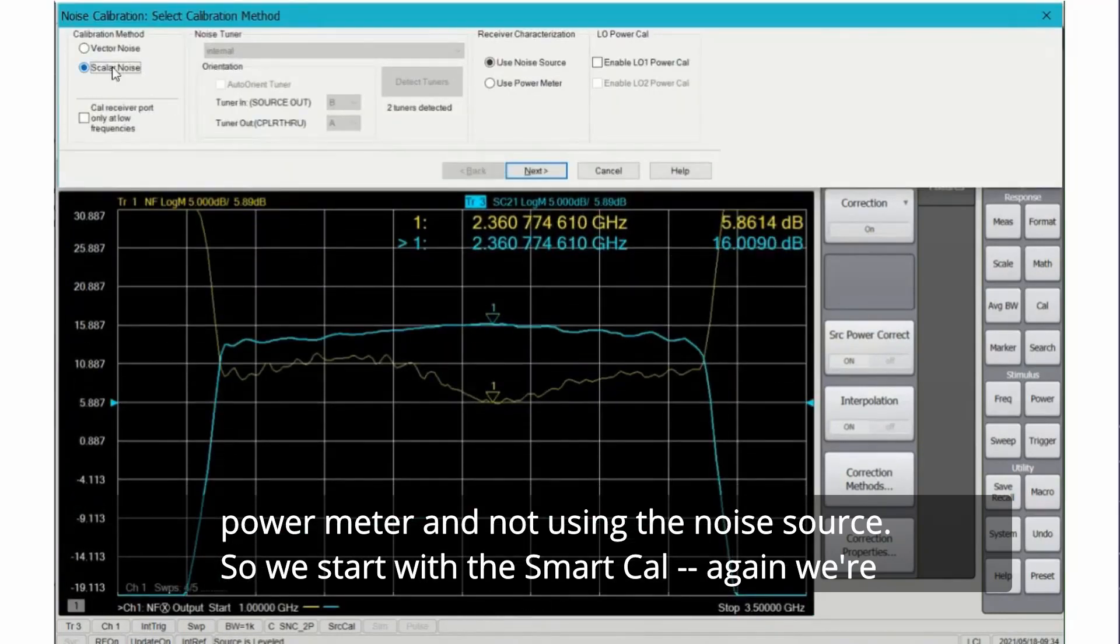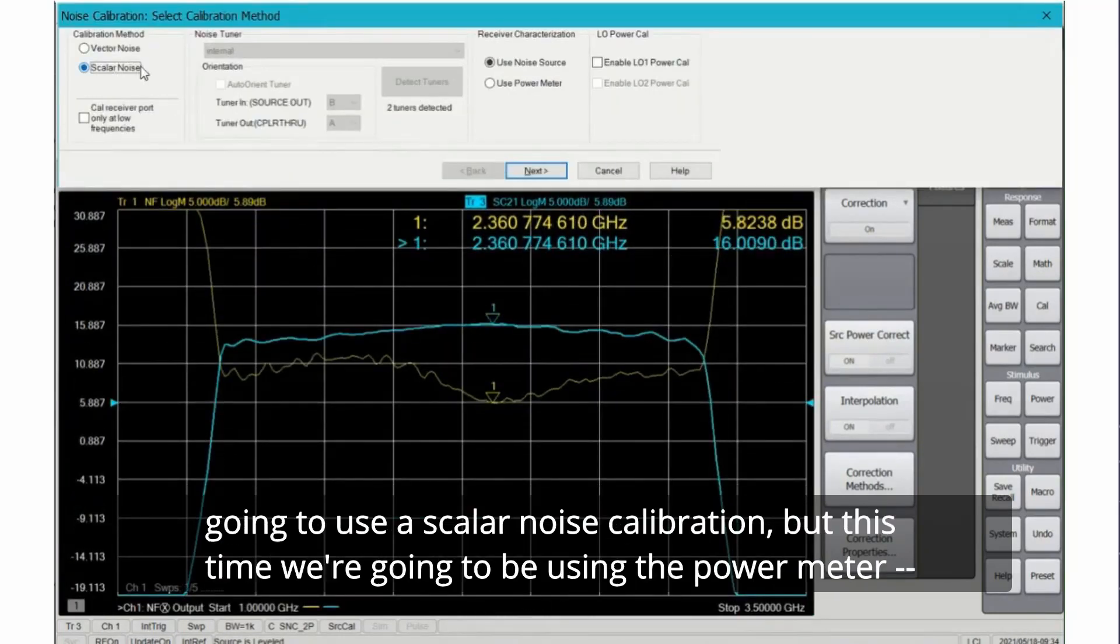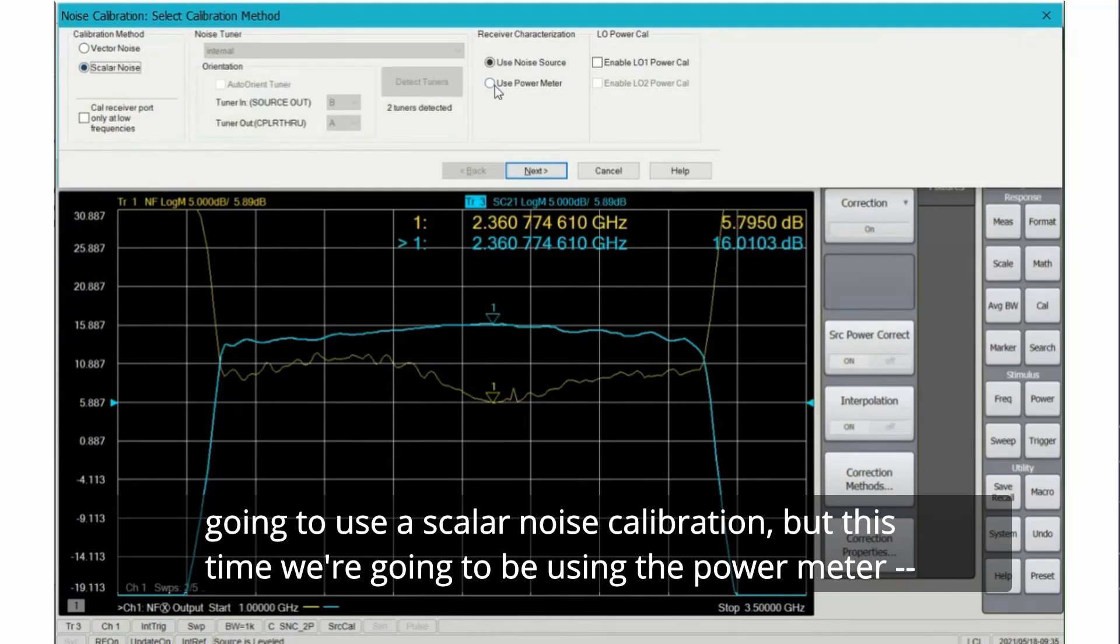So we start with the smart cal. Again we're going to use the scalar noise calibration, but this time we're going to be using the power meter.